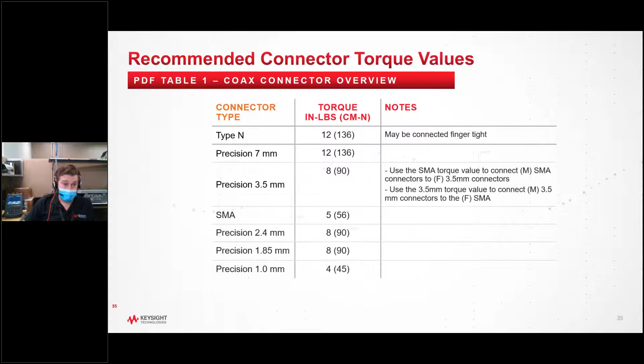So don't use pliers, use alcohol and lint-free swabs. Don't use a higher frequency connector than you need because it doesn't help you. It just adds complexity and expense. One thing I didn't mention earlier is never use a calibration kit as an adapter, ever. This will get you in trouble.